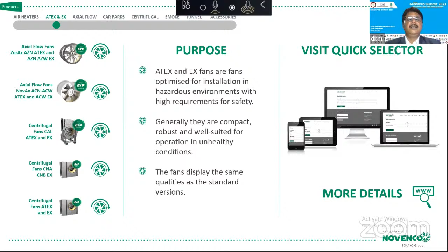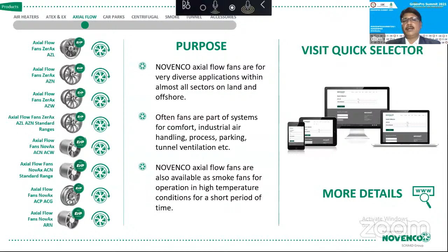We also have axial flow fans for different applications, like ZerAx fans and axial flow fans for AZN. With our fan you can achieve from 1200 CFM to 3 lakh CFM with a single fan, and static or total pressure from 15-20 mm up to 250-300 mm of water gauge. So there is a very wide range available in our product range.